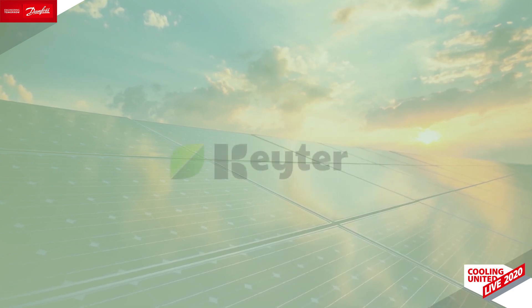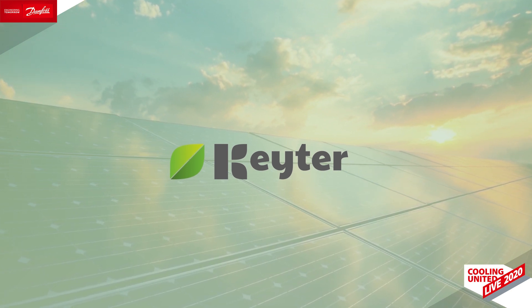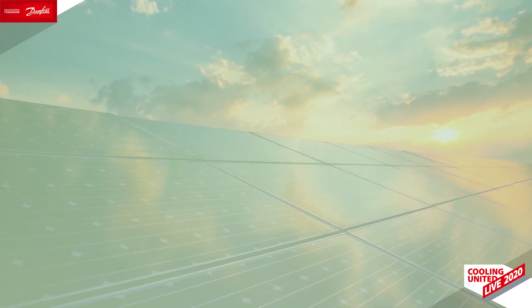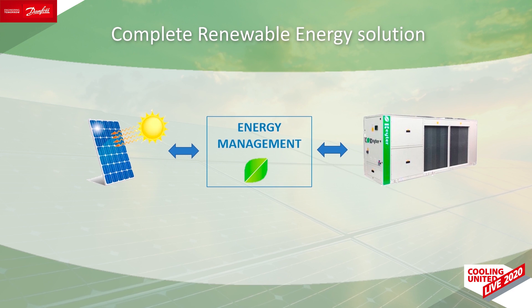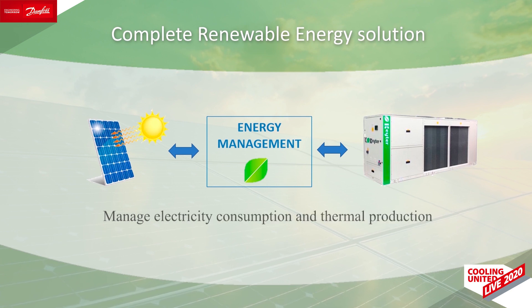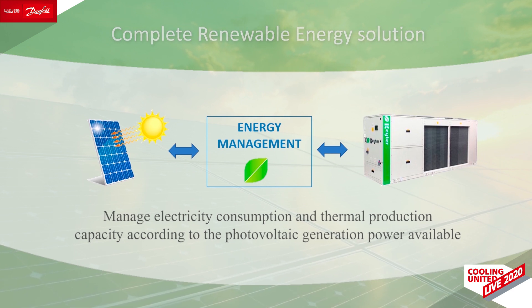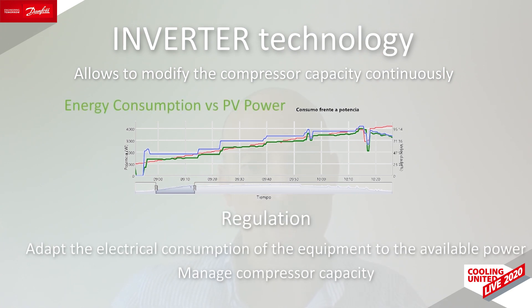Also, regarding sustainability, thanks to inverter technology, Keyter has developed an innovative and smart energy management system that allows integration with photovoltaic installations, resulting in a complete renewable energy solution. The unit is able to manage electricity consumption and thermal production capacity according to the photovoltaic generation power available at any given time. The inverter technology allows continuous modification of compressor capacity, and the regulation adapts the electrical consumption of the equipment to the available power and also manages the compressor capacity.